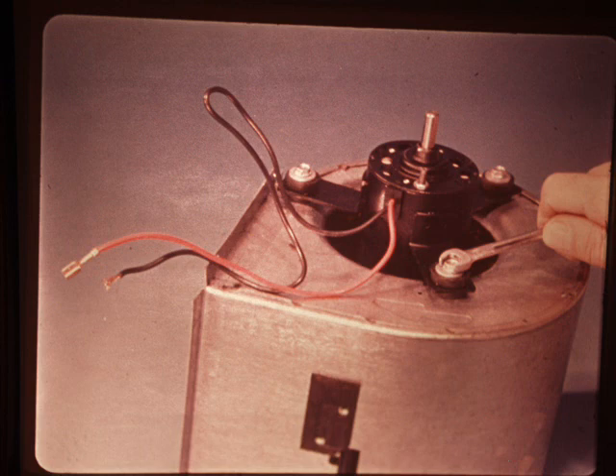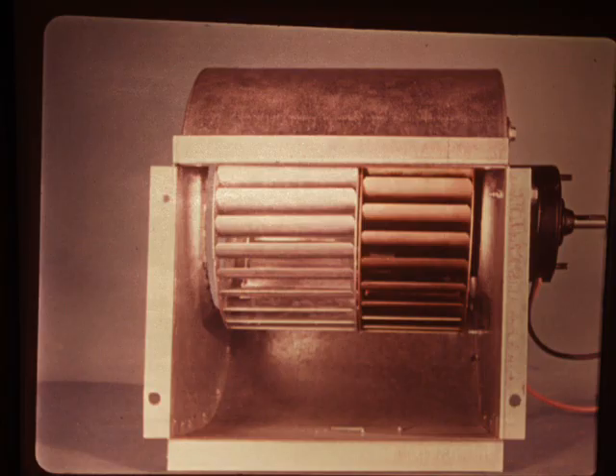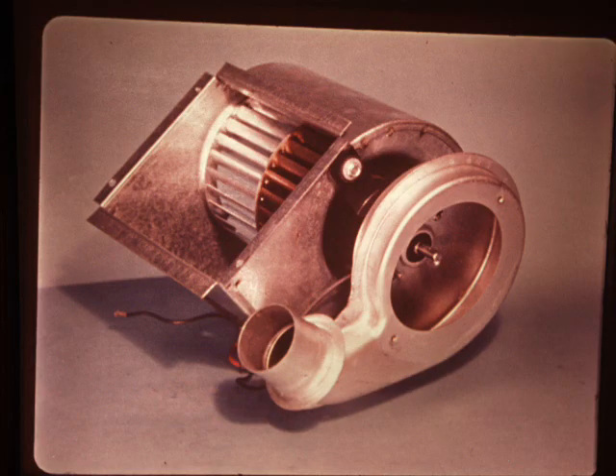When reassembling, be sure to place the motor with the electrical leads facing the blower housing mounting flange. Check that the recirculating air blower wheel clears both sides of the housing. Also, be sure the retaining screw is tightened onto the flat surface of the motor shaft. Check the inner combustion air housing for proper position in relation to the blower housing as shown here.